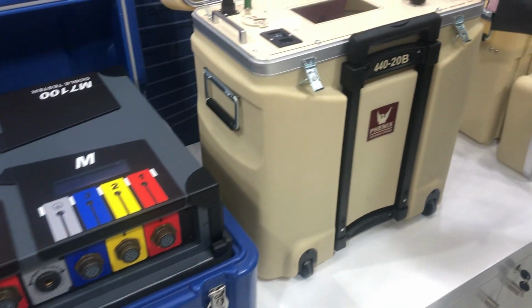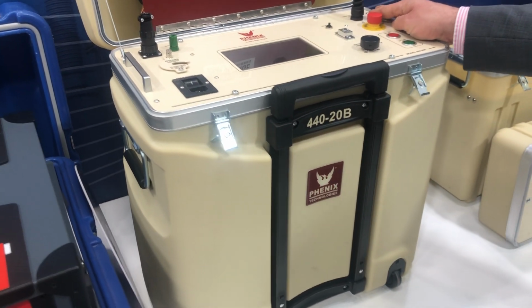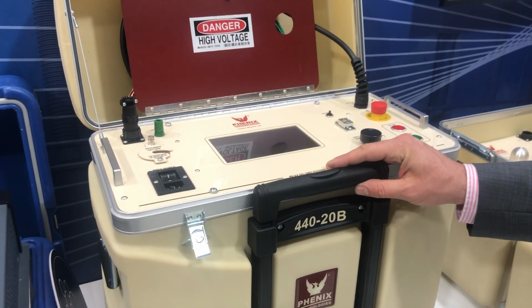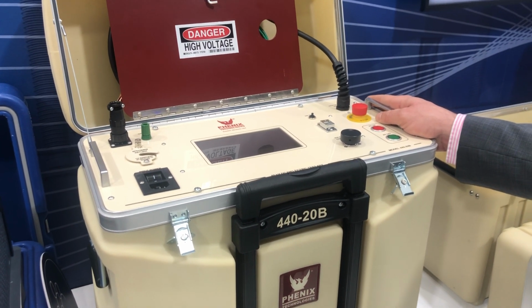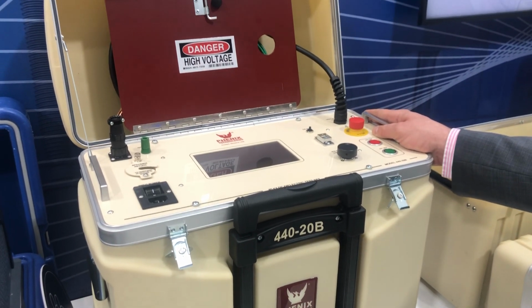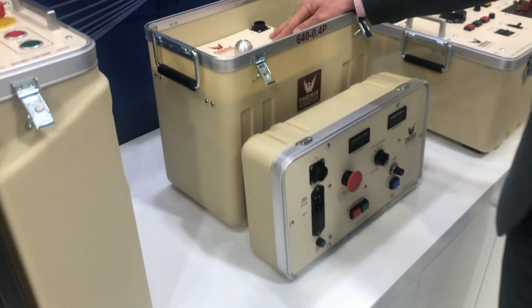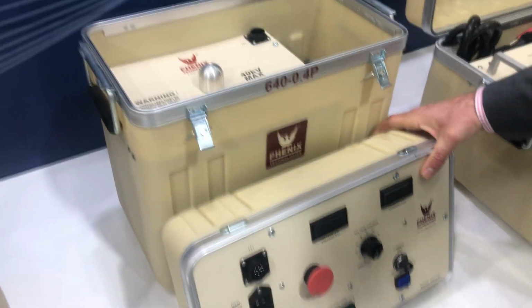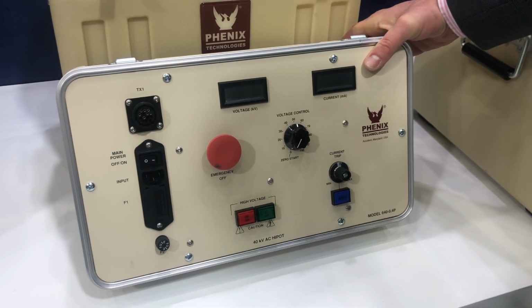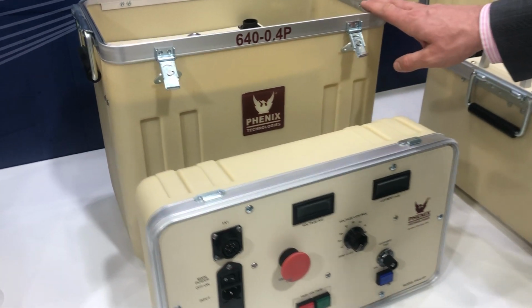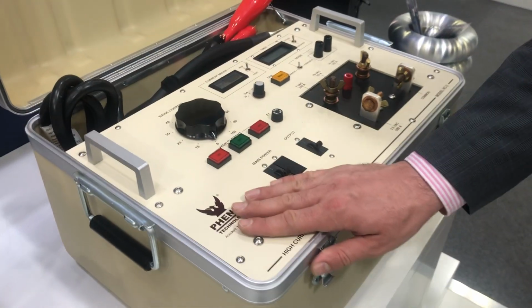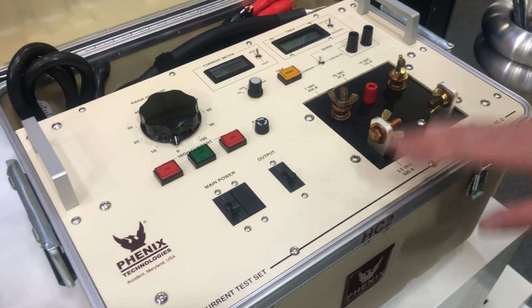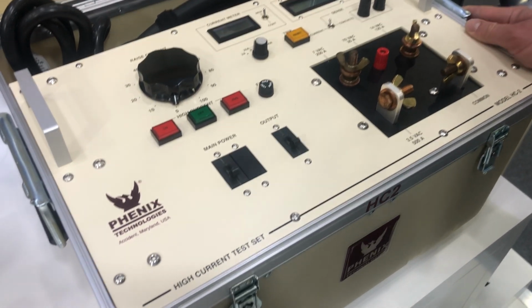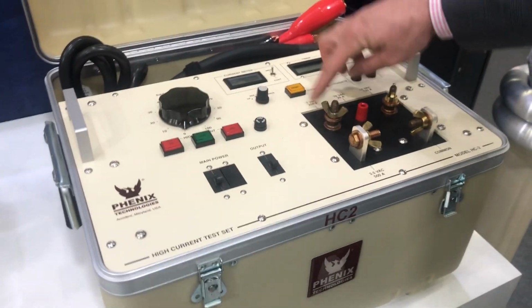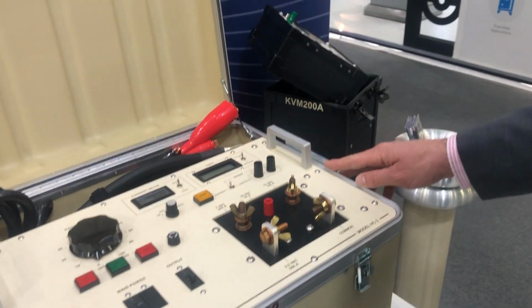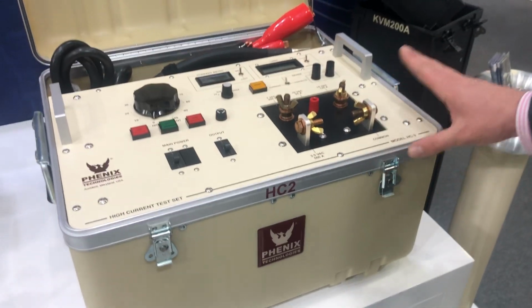And then we're coming to the Phenix that rose from the ashes. I mean, the Phenix which is here is the 40 kV DC hypot. So this is to test insulation with a DC method. And then we have also, up to 40 kilovolts, an AC method to test all kinds of equipment, as I mentioned, with the AC voltage, so 40 kilovolts max. And then if you need high current to test circuit breakers, to trip them, or maybe to test motors, with this device, HC2, you can go up to 500 amps. Of course, there are ranges up to 250, 125, and 25. Sorry, 2000 amps. That was my bad.